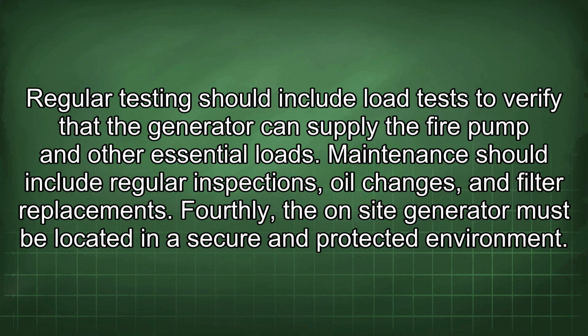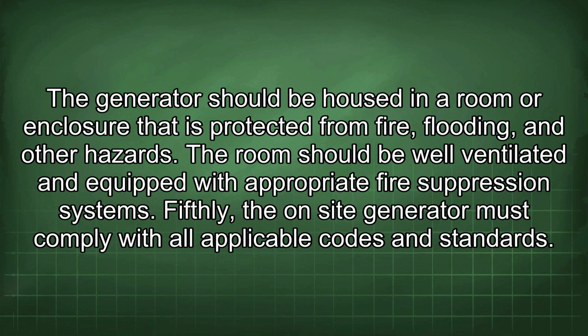Fourthly, the on-site generator must be located in a secure and protected environment. The generator should be housed in a room or enclosure that is protected from fire, flooding, and other hazards. The room should be well ventilated and equipped with appropriate fire suppression systems.